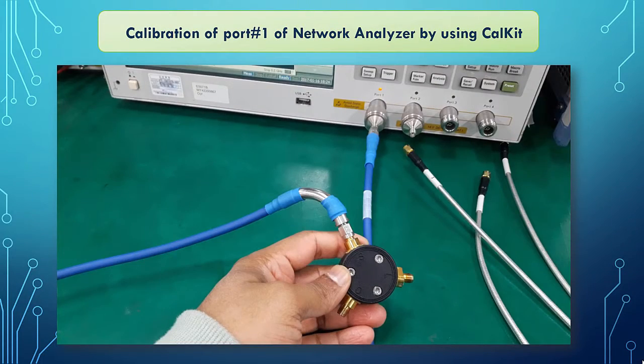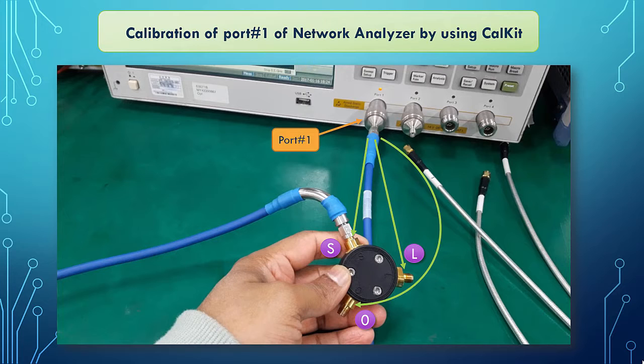So let's have a quick glance of calibration process. This is the port 1 of network analyzer and what I'm going to do is that I'm going to connect the port 1 with these three terminals of the cal-kit one by one and calibrate the port 1. Each time you want to use any port of the network analyzer, you have to calibrate that port using this device.